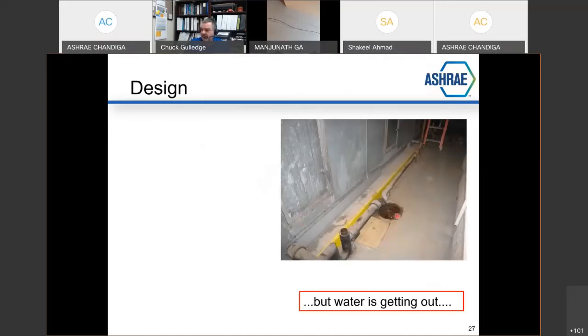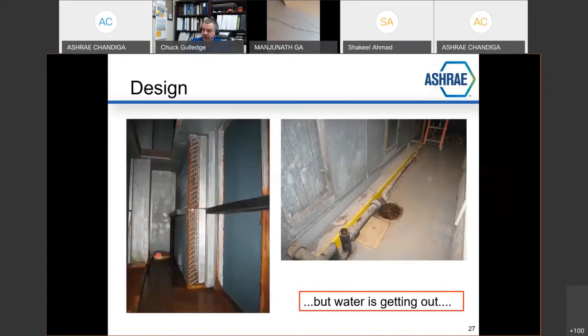But water is getting out. Look, you can see there is water getting out. Okay. We all agree there's a little water getting out. Look at the depth of this P-trap right here on the drain pan for the cooling coil. What do you see inside the cooling coil? It's a lake. It's full of water. All of this because somebody, and this happens to be a draw through, so air is going this way through the unit, through the cooling coil, and toward the fan to the left.